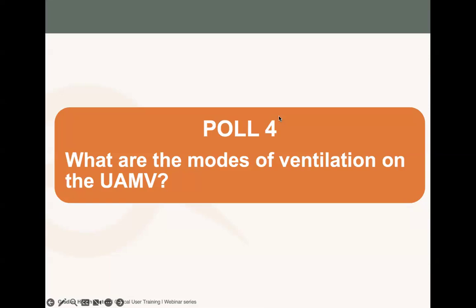Yes, thank you, Dr. Filippo, for that question. So when you are looping this machine, it is when the UAMV is faulty. It's not when you are just doing manual ventilation. If you are doing manual ventilation, you can just turn your switch to bellows, and then the gas will all pass to the ventilator and then to the breathing block. But when you are looping, this is only for emergency cases, when the ventilator has gone off and you can't use the vent. It's when you do the looping.